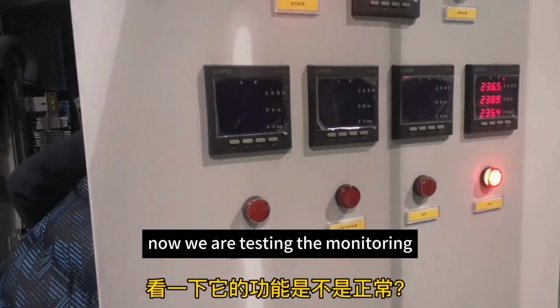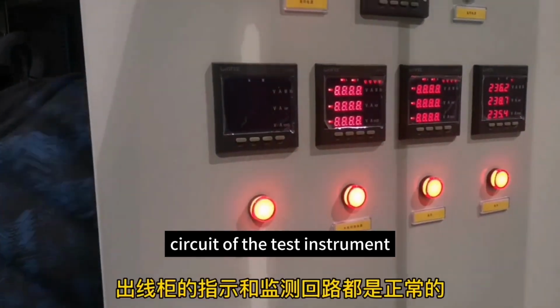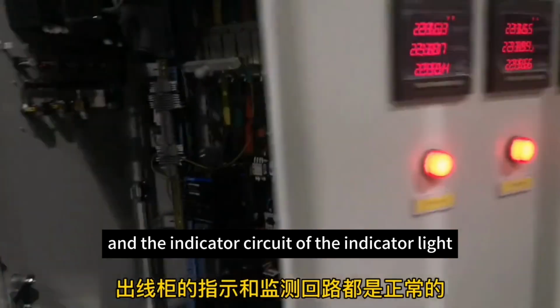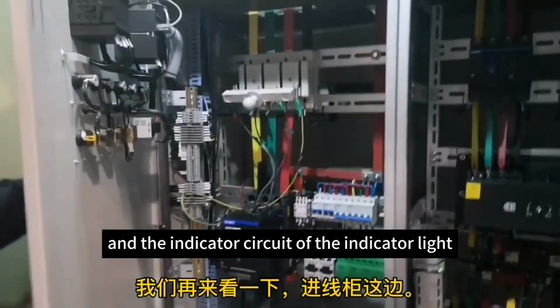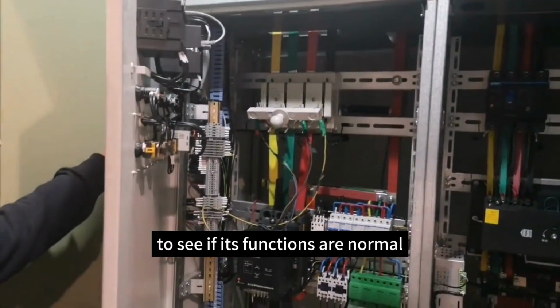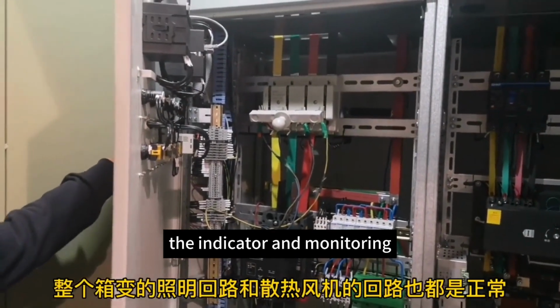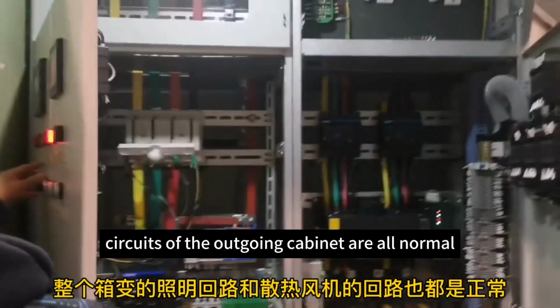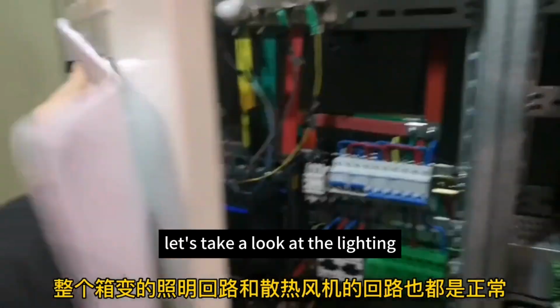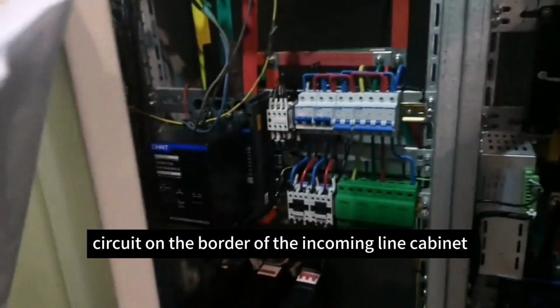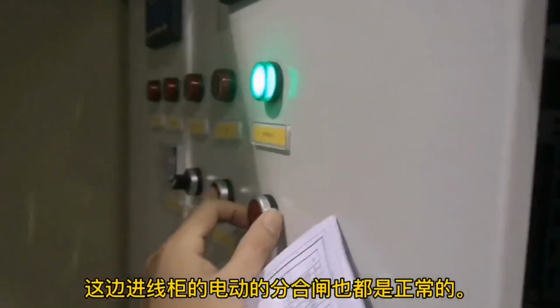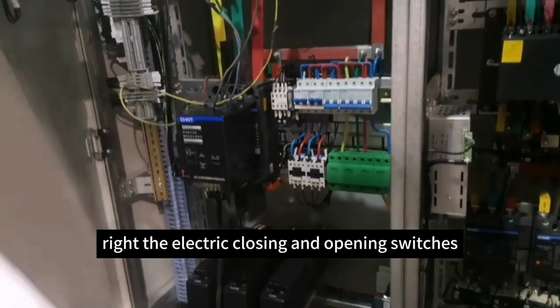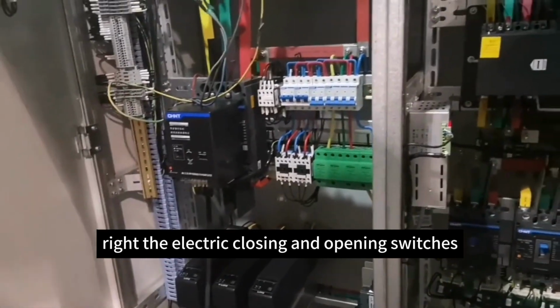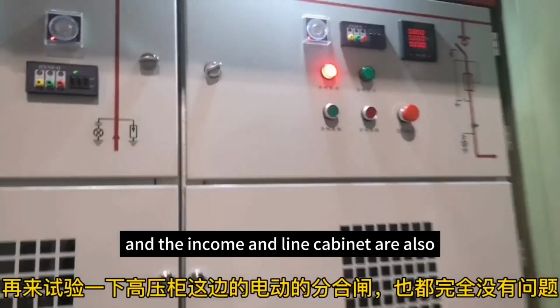Now we are testing the monitoring circuit of the test instrument and the indicator circuit of the indicator light to see if its functions are normal. The indicator and monitoring circuits of the outgoing cabinet are all normal. Let's take a look at the lighting circuit on the border of the incoming line cabinet and the circuit with the fan installed. The electric closing and opening switches in the incoming line cabinet are also working normally.